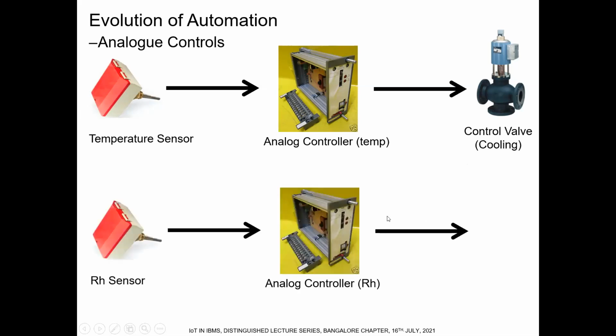So when we had to do humidity and temperature, those days the analog controllers had certain shortfalls because a controller could be connected only to one control device. So you could not compare the demand for cooling and the demand for dehumidification to drive a cooling valve. Those days they drove a heating valve whenever the RH increased, either an electric heater or an electric control valve supplying more hot water to the conditioned space. This was a wastage of energy, but that was the only way it was possible those days because of analog technology, because one controller could handle only one parameter.